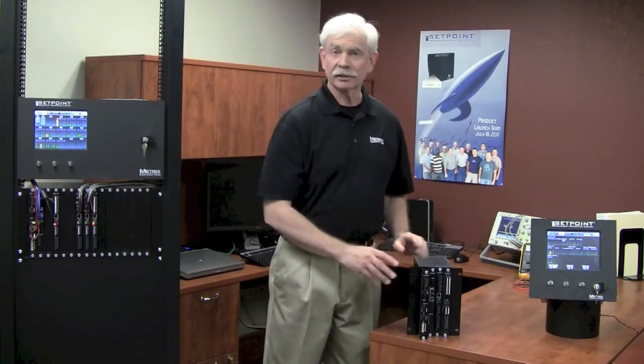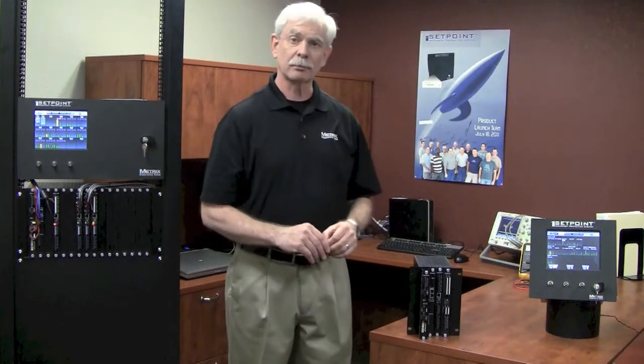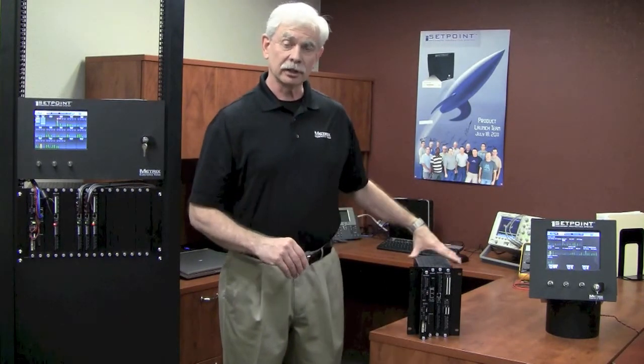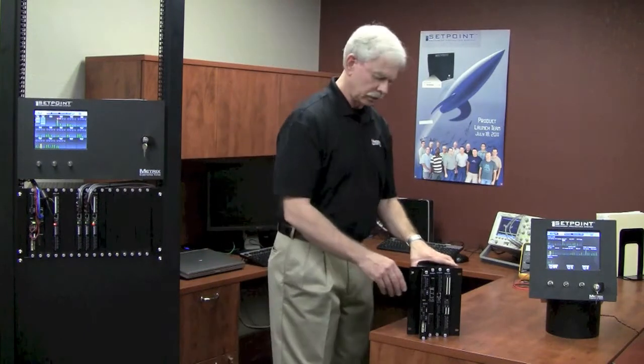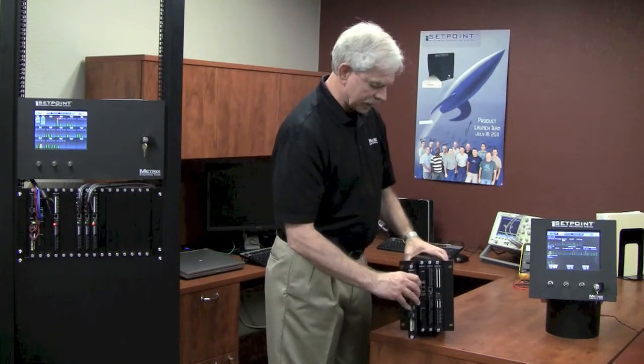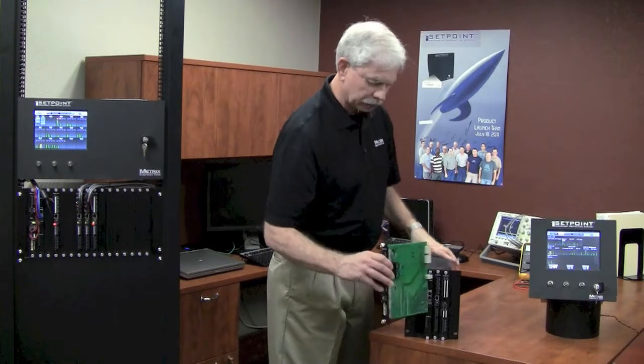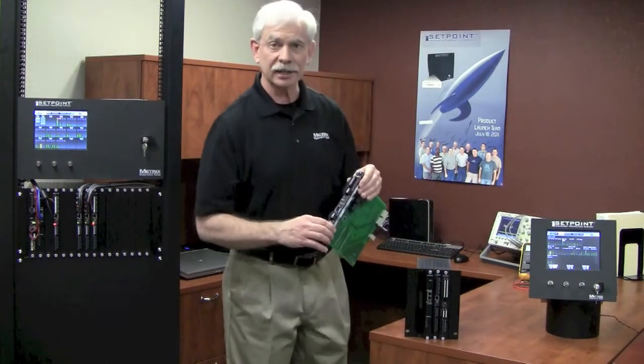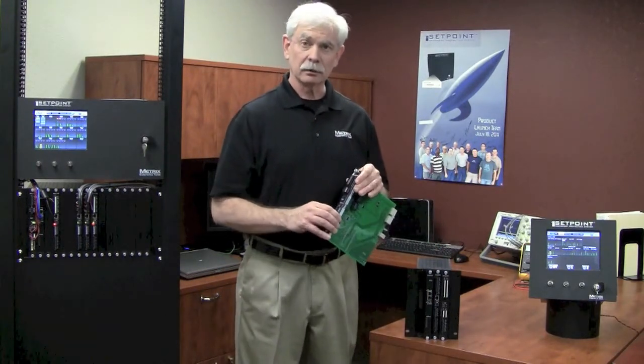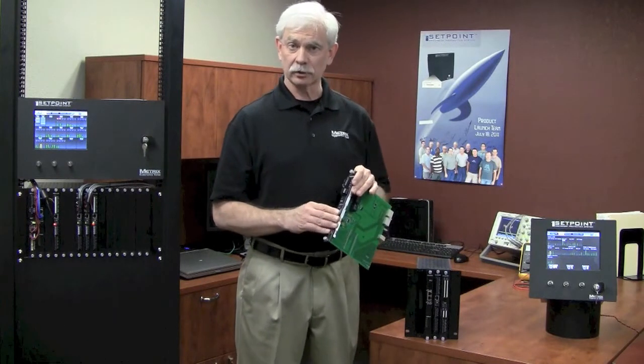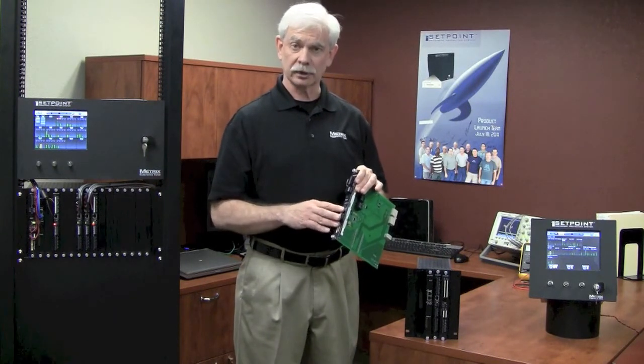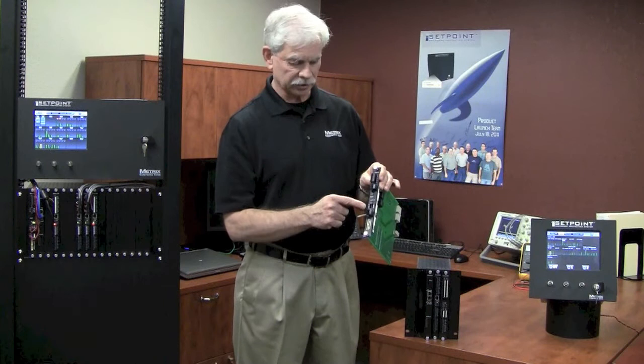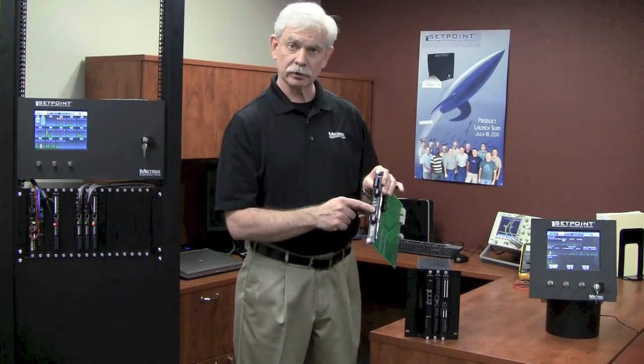Today we'd like to talk about the various module types that are used in the SETPOINT system. And to do that, we're going to rely on our little four-position rack here. Let's take a look at the leftmost slot. That is occupied by a module we call the Rack Connection Module, or RCM. The Rack Connection Module is basically used to bring 24-volt power into the rack. We have two connections, power 1 and power 2.